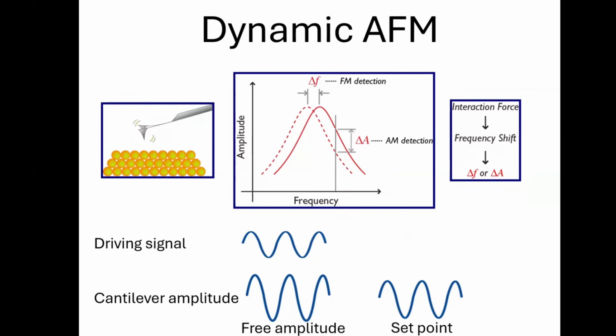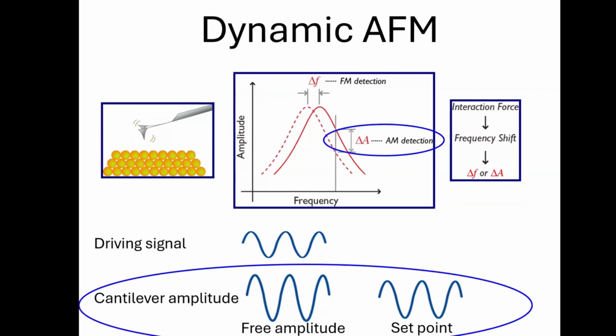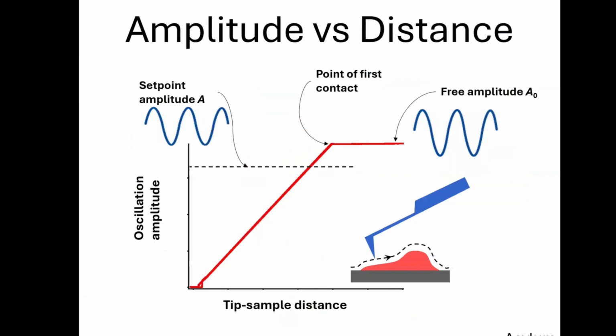If the amplitude is reduced significantly, the set point is small. And if the amplitude is reduced only slightly, the set point is large. It's very close to the free amplitude. This is shown nicely here. It's like an amplitude versus distance curve. We start far from the surface with our free amplitude. As we start approaching the surface, it stays the same until we start interacting with the surface, and then it reduces. The amplitude will decrease. We might choose a set point or amplitude reduction here to do our imaging. If we happen to keep going closer and closer to the surface, our amplitude will continue to decrease.